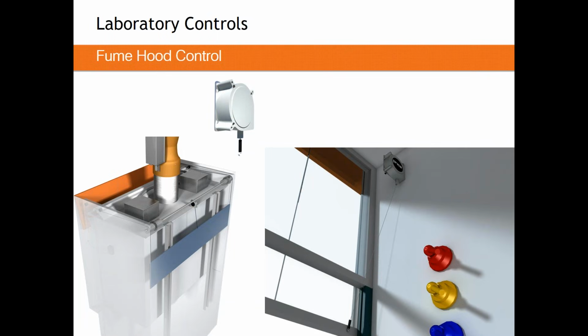So in the back of a vertical sash hood, you'll have a counterweight. On the image on the left, that's what's shown in blue. The easiest way to control these hoods is to take a stainless steel drawband cable and mount it to that counterweight. The counterweight will move linearly with the sash, and basically what it will do is measure how much open area we have. Sash sensing is essentially that. We measure the open area. We already know the width of the hood because it's not changing, and we now have measured the height, so we get an open area in square footage.